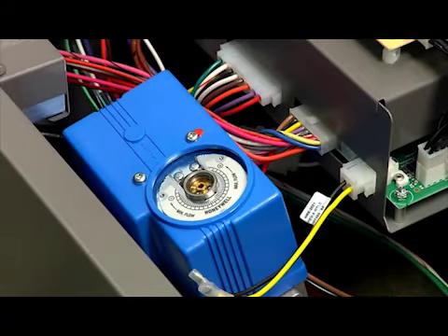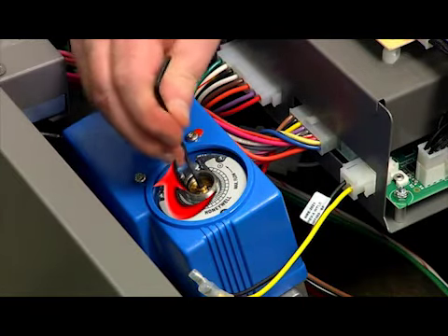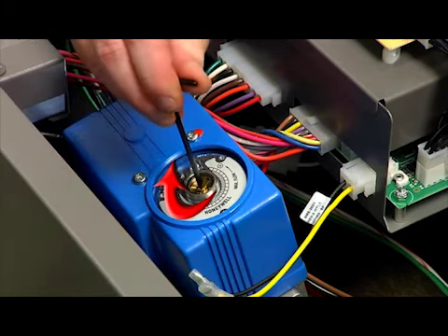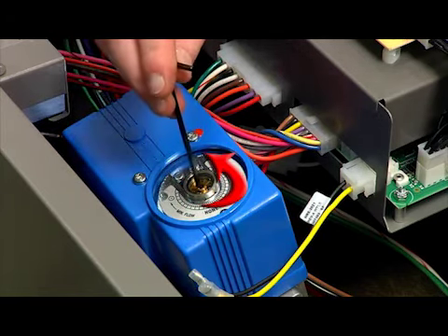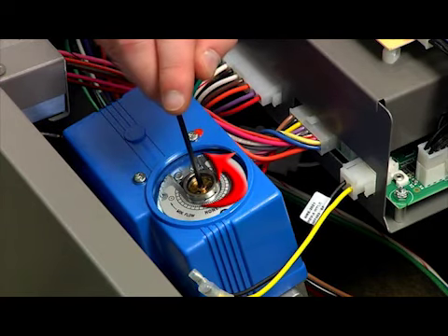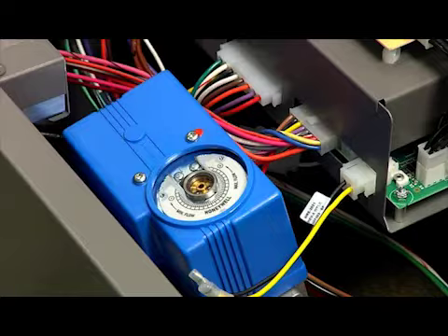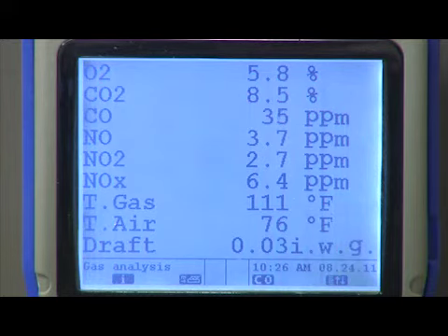Using a 3 mm Allen wrench, turn the adjustment screw 1/4 turn clockwise to decrease CO2 levels, and 1/4 turn counterclockwise to increase CO2 levels. After one adjustment of the valve, allow the combustion to stabilize and recheck the CO2 and CO levels. If the CO2 and CO levels are still not within the specified range, repeat the adjustment procedure. If after 4 adjustments the CO2 and CO levels are still not within the specified range, revisit the other possible causes or replace the gas valve.